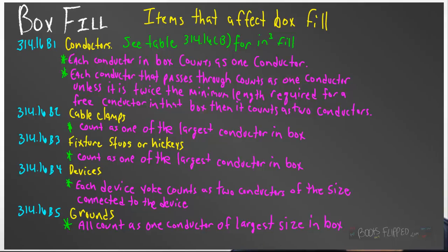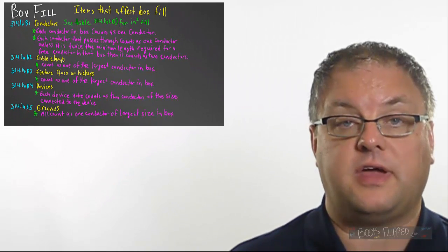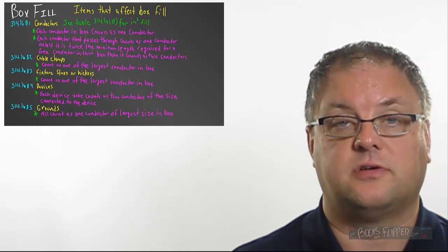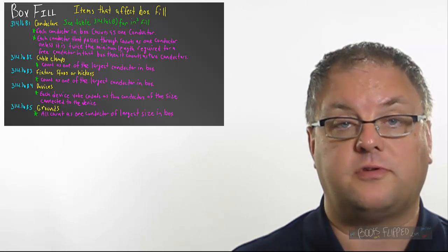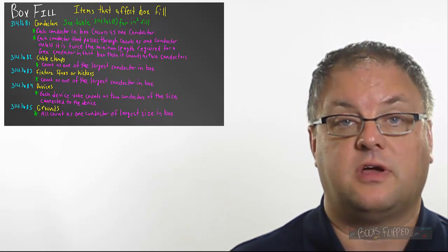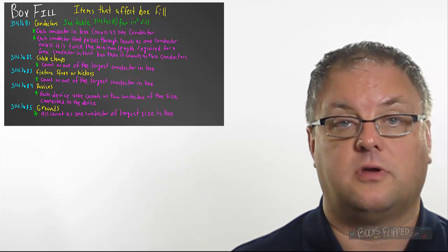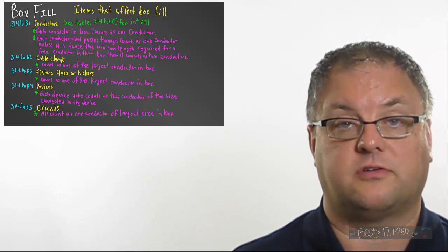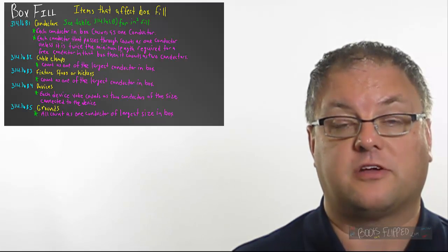In 314.16B4, then we talk about devices. And here's one that I want to make sure that you understand well. Every device counts as two conductors of the size of conductor that is connected to it. There are cases, especially in the kitchen, where you're going to have a number 14 conductor in a box and a number 12 conductor in the same box. And if your device has the number 14s connected to it, then that device counts as two number 14 wires. Your other device, if it has the number 12s connected to it, counts as two number 12 conductors. So, remember that when you're doing your box fill calculations.